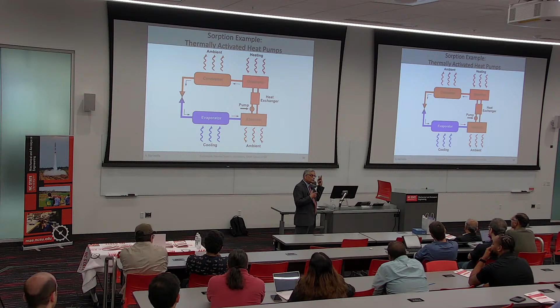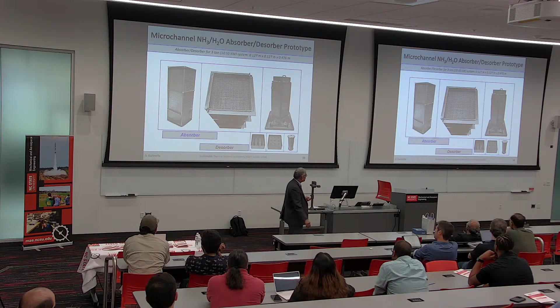But we worked on miniaturizing these using our insights into heat and mass transfer that I presented earlier. For example, through our insights into tube-side microchannel flow and falling films, we came up with this concept years ago, where you pour dilute liquid down a crisscross matrix. Due to that crisscross nature there's plenty of mixing, and a lot of absorption happens. The vapor is sent from below to the top and gets absorbed, and the heat of absorption is sent through microchannel tubes with high heat transfer coefficients, resulting in a fairly small package, about 5 inches by 5 inches by 12 or 13 inches. You put four of these together and that gets you a heat pump, which can do absorption, desorption, evaporation, and condensation.